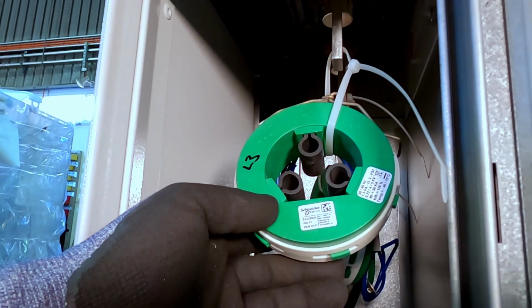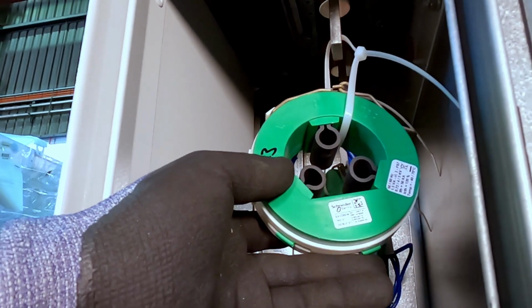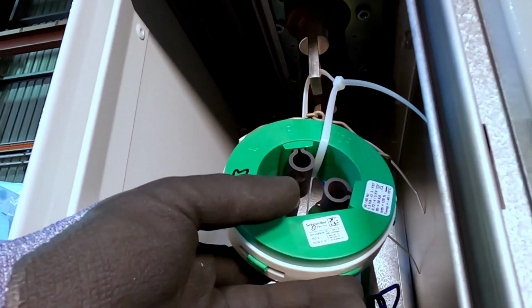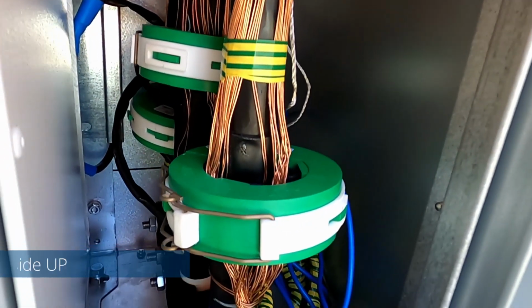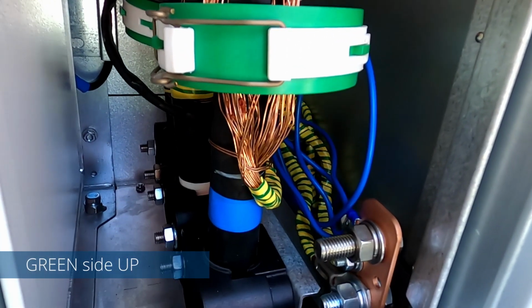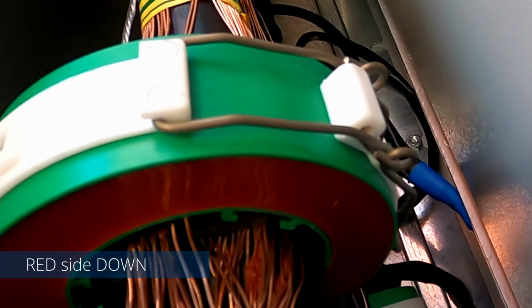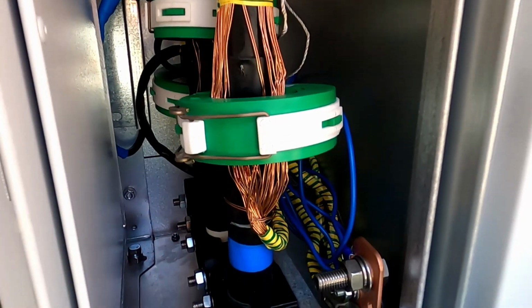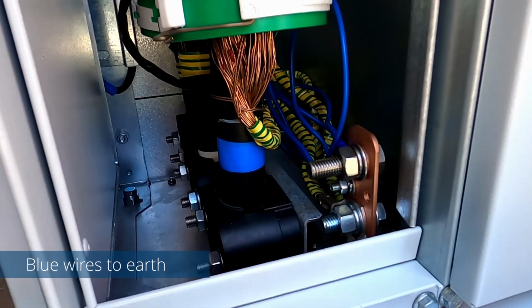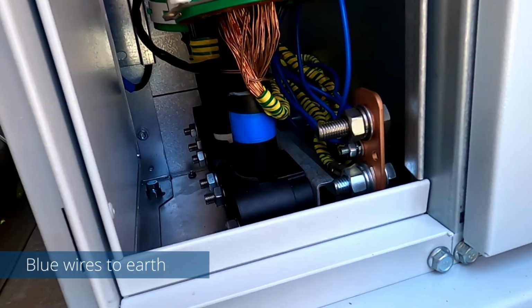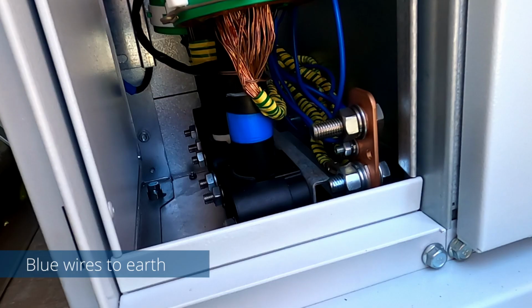The CTs are labelled L1 to L3 and should be installed to the corresponding conductor. They are directional and should be installed with the green side facing up and the red side facing down. In addition to cable screen connections, ensure the blue wires from the CTs are connected to the earth bolt connection.